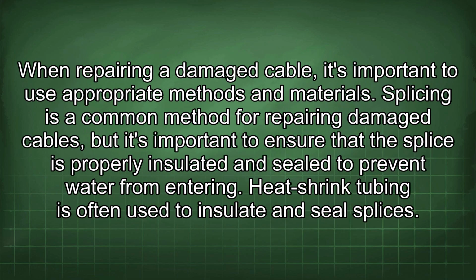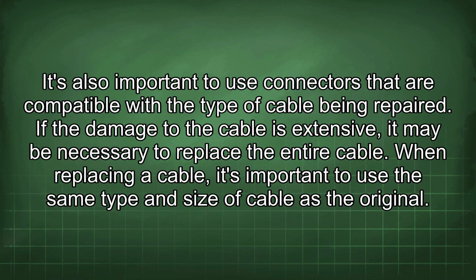When repairing a damaged cable, it's important to use appropriate methods and materials. Splicing is a common method for repairing damaged cables, but it's important to ensure that the splice is properly insulated and sealed to prevent water from entering. Heat shrink tubing is often used to insulate and seal splices. It's also important to use connectors that are compatible with the type of cable being repaired.